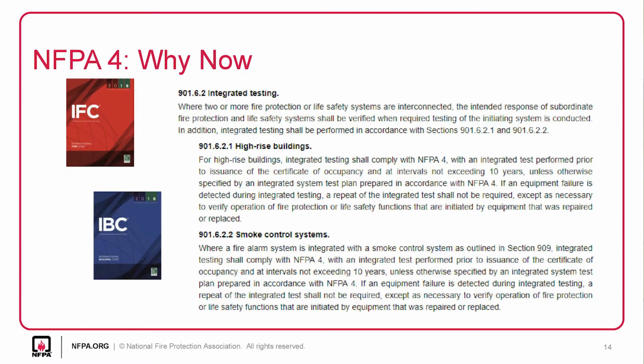Does anyone have any questions on what I've been over so far? A quick question. Let's say you have a small smoke control system. Does that mean you have to do integrated testing for fire doors and the kitchen hood system? You have to do everything, yep, not just that smoke control system. Yeah. Where a fire alarm system is integrated with a smoke control system as outlined in 909, integrated tests shall be performed per 4.